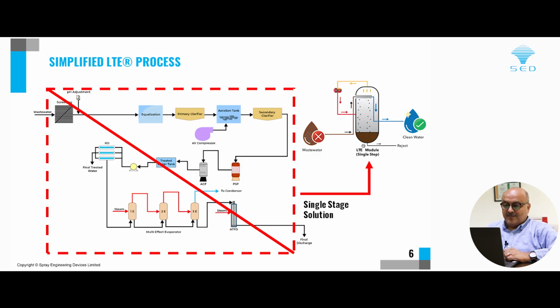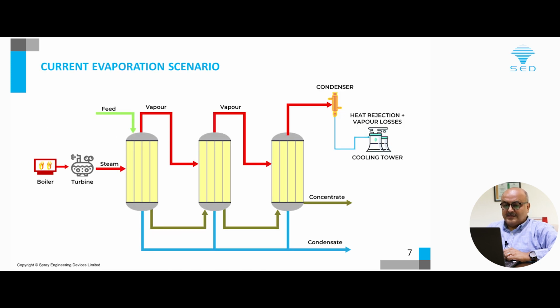This is a scenario from us, where the whole of the process is actually being considered as eliminated. We are taking the wastewater directly from the process house and screening it, and then setting the pH and taking it into the low temperature evaporation process. This is a current evaporation scenario where the boiler or a turbine is required. Basically the heat is required, and the heat is rejected via the condenser and the cooling towers.